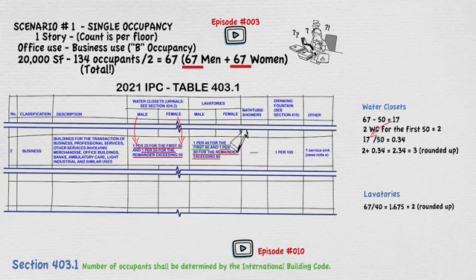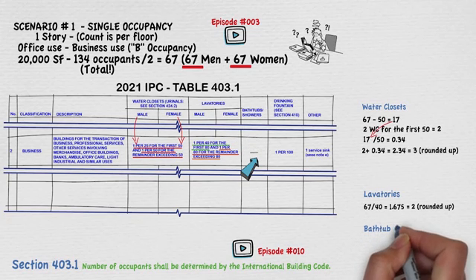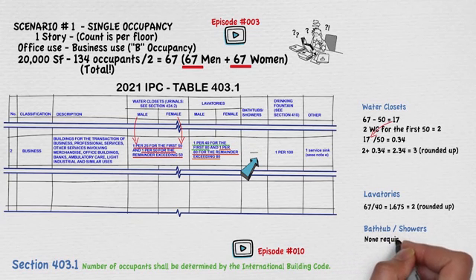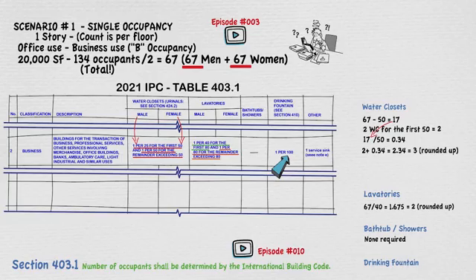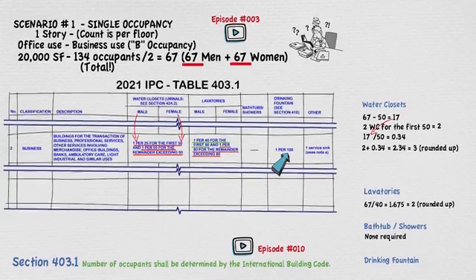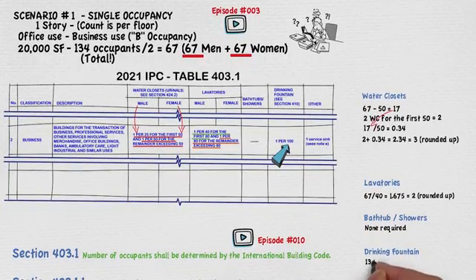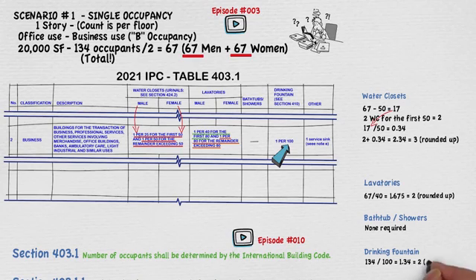The next column is for bathtubs and showers, but there are no requirements, so none are required per the plumbing code. The next column is for drinking fountain requirements, which states 1 per 100. Note that this is no longer divided by male and female, so we use the total number of 134 divided by 100, which equals 1.34. We round up, so 2 drinking fountains are required.